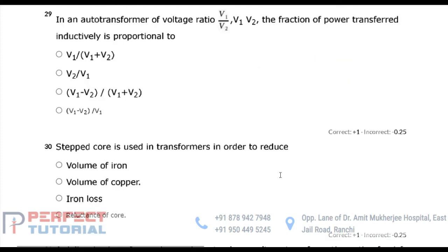Next, look at the question. In an auto transformer of voltage ratio V1 by V2, the relationship between V1 and V2 should be given, and let's see the correct relationship. That should be V1 is greater than V2. If V1 is greater than V2, there are two possibilities. If V1 is greater than V2, it means the LV of the auto transformer will be V2 and the HV will be V1. Meaning the K value would be equal to V2 by V1. If so, then the power transferred inductively is asked. Power transferred inductively is proportional to the factor 1 minus K.